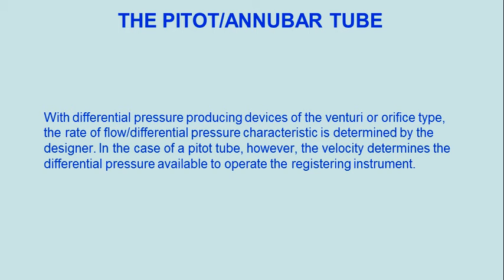With differential pressure producing devices of the venturi or orifice type, the rate of flow versus differential pressure characteristic is determined by the designer. In the case of a pitot tube, however, the velocity determines the differential pressure available to operate the registering instrument.